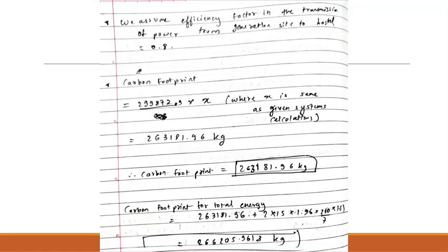Now we again take the efficiency factor for the transmission of energy to be 0.8, and to calculate the carbon footprint for the proposed system, we plug in the required energy of the hostel for the new system. From the below expression, we have the carbon footprint for the new system to be 263,181.96 kilograms, which is significantly less, around 1.5 times less from 450,000 around that we had for the initially suggested system for the hostel. So just the given changes make so much change in the carbon footprint and also in the required energy for the hostel.